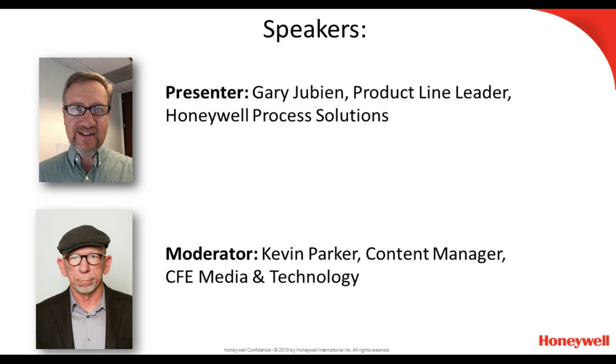So the accumulation of benefits starts at the kickoff meeting, in my opinion, on an APC project. I've heard it suggested that, well, we're going to commission the controls, and then a month later, I'm going to turn them off and then see where the process goes and measure it. In my opinion, that's sort of shortchanging the value of APC itself. The proper conditions for the baseline are actually before the kickoff meeting of the APC project ever happened. And then the other point is that there is a cost to doing that. If you believe the APC is delivering benefits, if you turn it off for a week or a month, then you've absorbed a lot of cost in proving that. So we'd rather advocate for something like a post audit that measures the APC performance and contrasts that to the pre-project performance as a better way of establishing the benefits of APC.